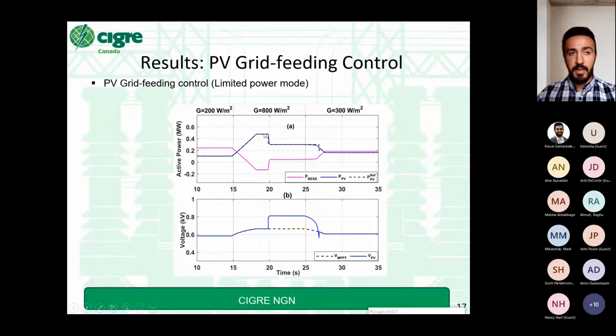Close to 20 seconds, the supervisory control anticipates an overcharge and provides the PV array with a supervisory power reference, and the PV here starts following its limited power mode reference. If we look at the PV voltage and the MPPT, we can see that the PV array voltage is higher than the MPPT, which is a curtailment mode. Close to here, as the irradiance drops from 800 to 300, we can see that the PV array exits limited power mode and starts following the MPPT reference, as also reflected here.